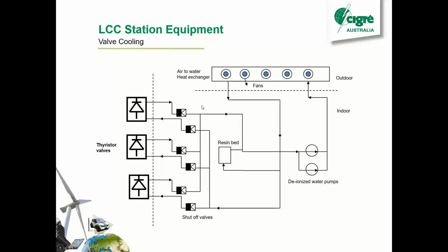So you pass water through them basically in plastic pipes. The issue with that is with your pumps and your fans, this is all at ground potential, whereas your thyristors are at high voltage. So you have to use what we call deionized water, which is water that's had all the minerals and impurities taken out. That really pure water is actually a pretty good insulator. In that case, you're okay. You're not going to cause any shorts. But if you ran tap water in this system, you'd basically short out your converter through the cooling system.